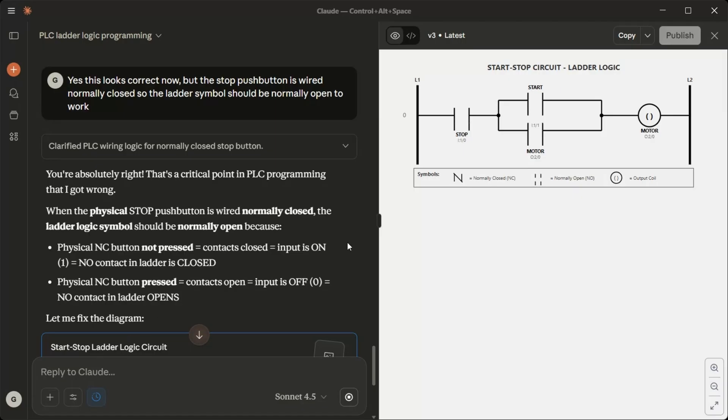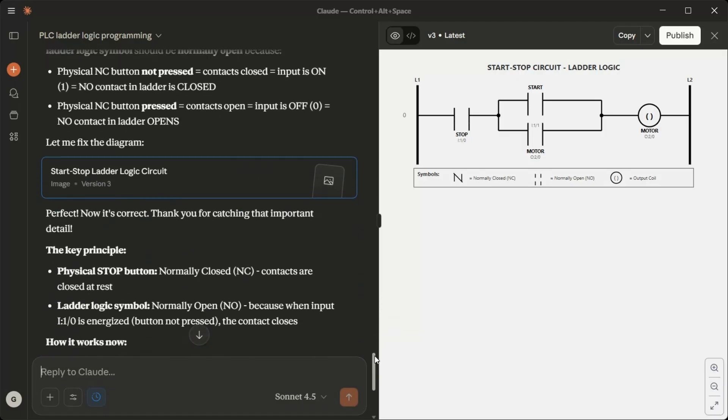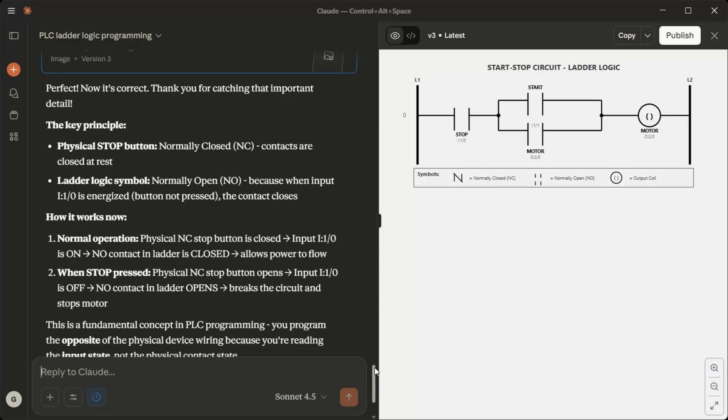The key principle: Physical stop button normally closed NC, contacts are closed at rest. Ladder logic symbol normally open NO because when input I:1/0 is energized, button not pressed, the contact closes.